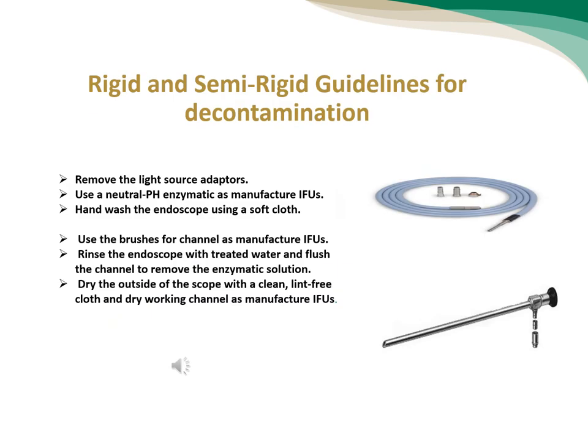Rigid and semi-rigid guidelines for decontamination: Remove the light source adapters, use a neutral pH enzymatic solution per manufacturer IFUs, hand wash using a soft cloth, use a brush for channels, and rinse the endoscope with treated water and flush the channels.